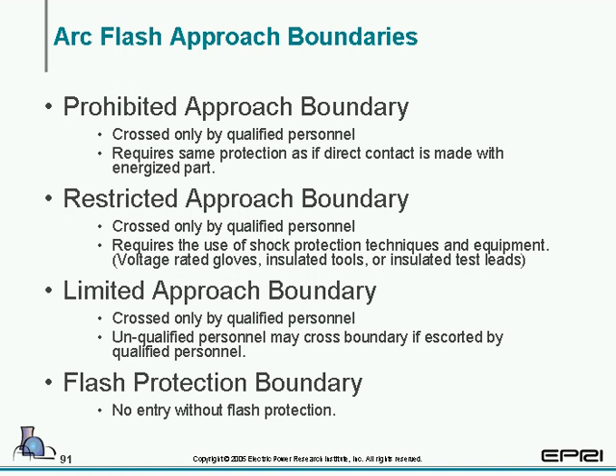You have a definition of each arc flash boundary, going from the top, which is the most restricted, to the bottom, the least restrictive. The prohibited approach boundary is crossed only by qualified personnel. It requires the same protection as if direct contact is made with the energized part. A restricted approach boundary is crossed only by qualified personnel and requires the use of shock protection techniques and equipment, such as voltage-rated gloves, insulated tools, or insulated test leads.